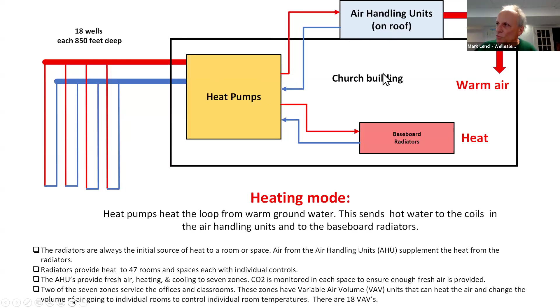One loop goes to our baseboard radiators, so that's always hot water when you're in heating mode. The other loop goes up to the roof, and in heating mode we're sending hot water up to the heating coils, which then send warm air down to our rooms. In the summer, this is a dual temperature loop. In cooling mode, it converts, and the heat pumps or the wells go directly to the roof with cold water, and cool air goes to the rooms. That's how the heating mode works.